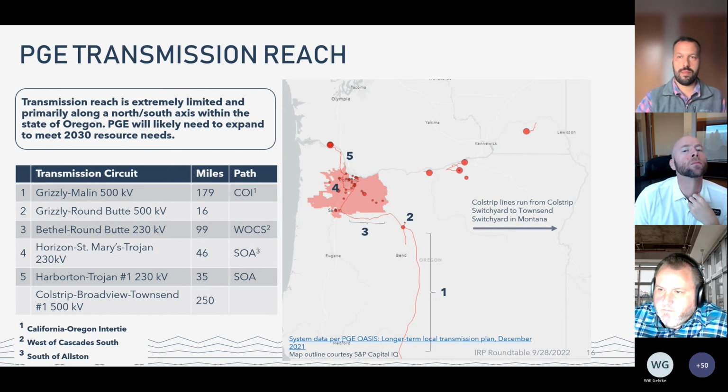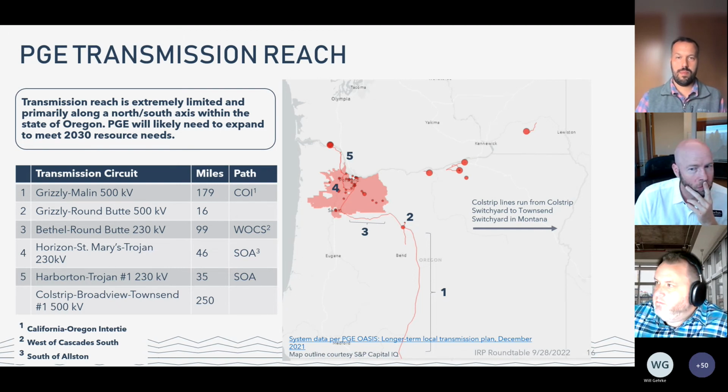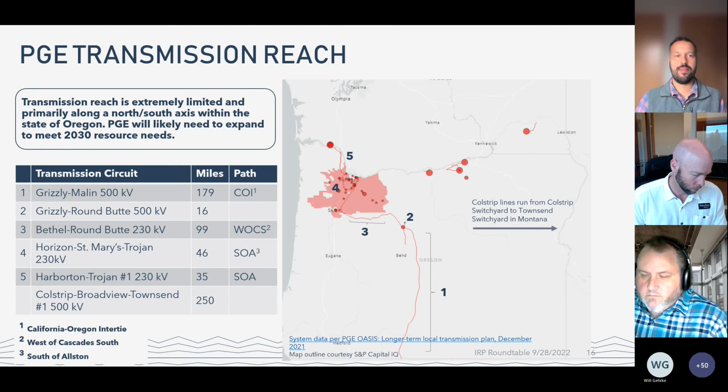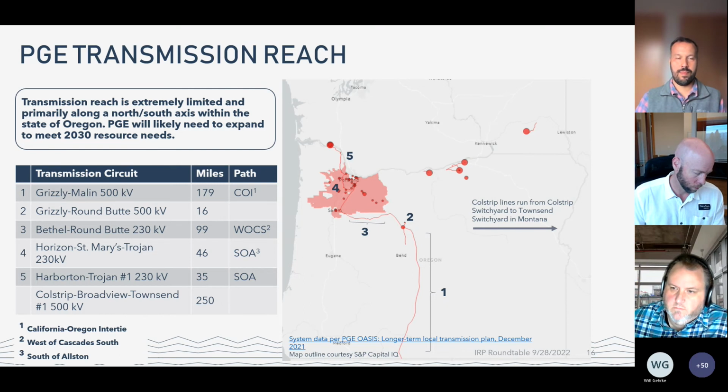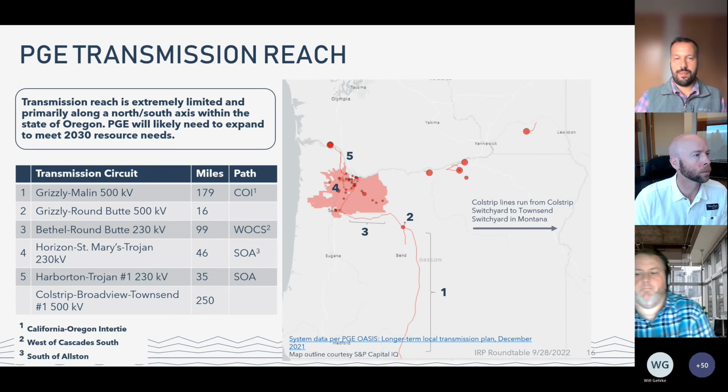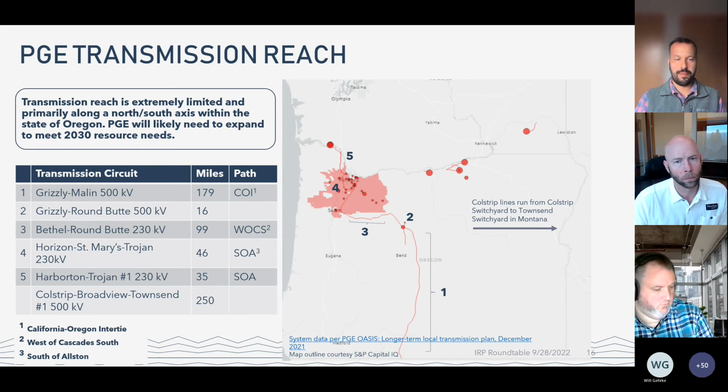Yeah, to continue this, but put a little different spin on it. Frankly, the Bonneville transmission planners, and I'm sure you all are aware of this as well, are more worried about Raver Paul than about south of Allston. Because when Centralia 2 retires in 2025, the south of Allston problem doesn't go away, but it gets significantly reduced. You have 670 megawatts of thermal power that no longer is trying to get south in the summer evenings. But that will shift the congestion issue, as I understand it, to Raver Paul. And in the 2021 cluster study, Raver Paul was the huge constraint. It wasn't this time around, but the loadings were within 100 megawatts of exceeding its TTC. So there's a whole number of questions, of which I'm sure you're aware. But looking at the effect of Centralia 2's retirement on the south of Allston / Raver Paul problem is a critical part of how you address this.